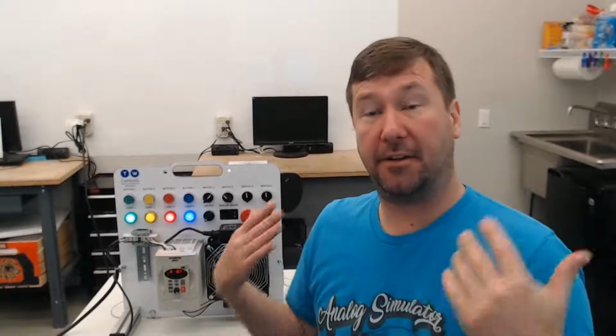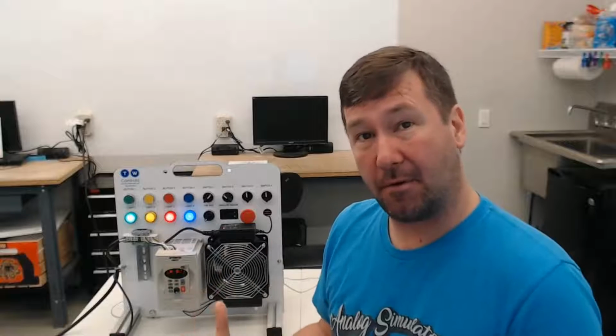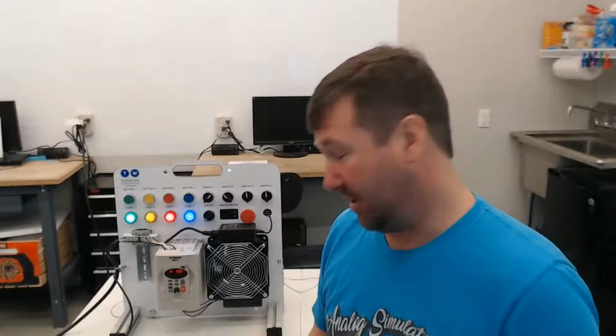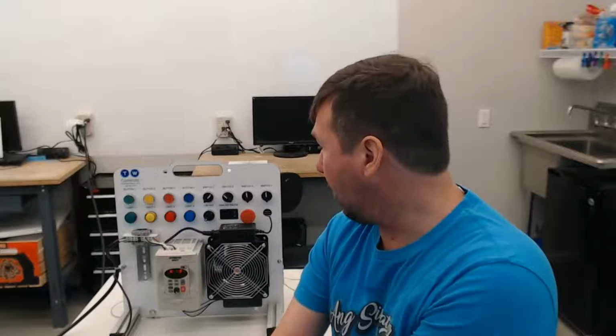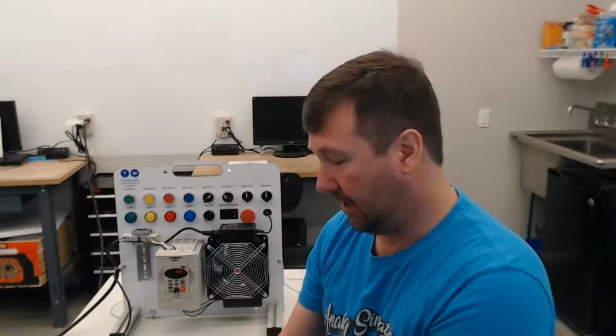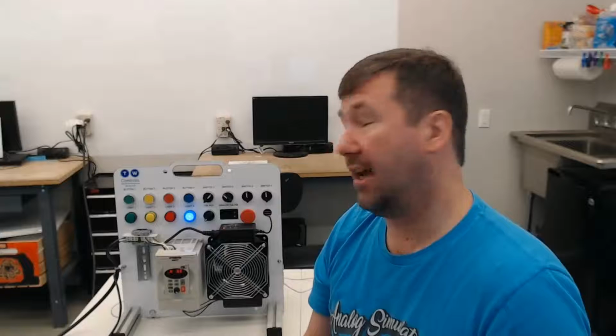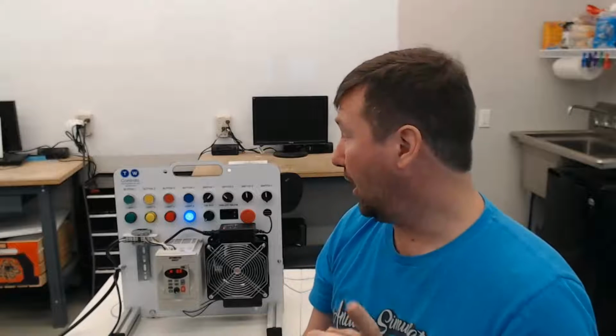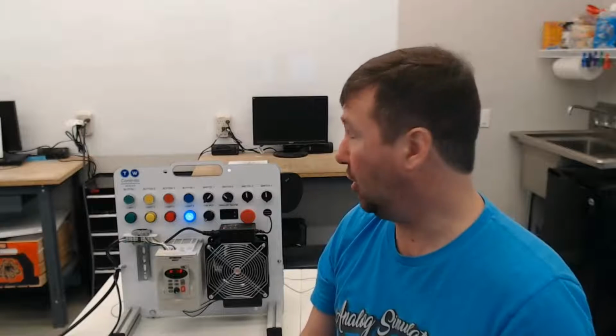Now, there is one other situation that you need to be aware of how these buttons actually operate, and that is during a power cycle. So I'm going to turn the power off to our trainer, and now I'm going to turn it back on. And you can see on power up, the green, yellow, and red lights, which are associated with rungs 0, 1, and 2, do not turn back on. But the blue light that is associated with rung 3 does turn back on. And we're going to go into the details of that in the next video.